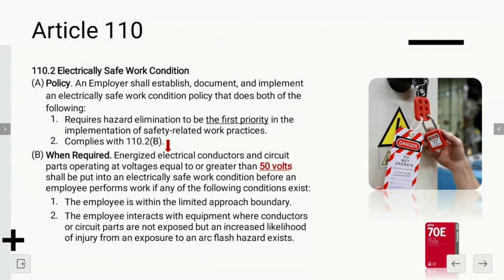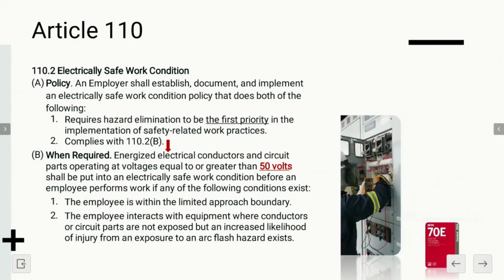Okay, now here's the other thing. The 70E says energized electrical conductors and circuit parts operating at voltages equal to or greater than, here's the magic number you need to remember, 50 volts shall be put into an electrically safe work condition if you're going to be in what's called the limited approach boundary, which we'll talk about in just a sec. Or if you're not exposed, but you're interacting with a piece of equipment that could cause or create an arc flash explosion. Okay. Notice it doesn't say AC or DC. Did you notice that? It's 50 volts. If you're going to be exposed to 50 volts or higher, all the rules apply. Make sense? So let's break this down a little bit here.